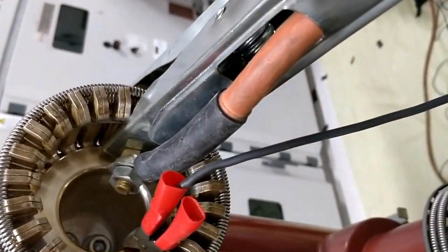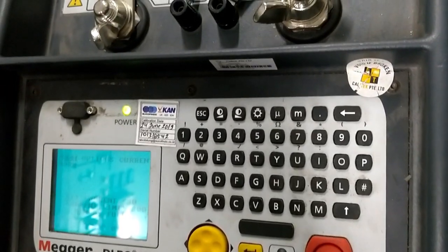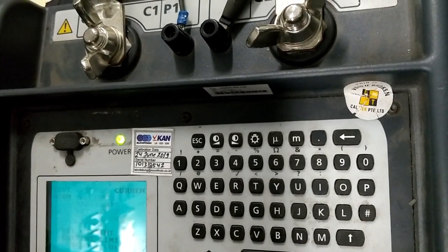Connect the current cable to the R phase from the in and out of the breaker and connect the voltage lead towards the current. Now I am going to start the contact resistance test in normal mode.